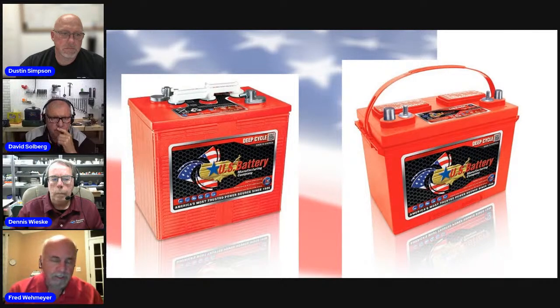Those load testers are really intended for SLI batteries. A true load tester will actually put a discharge on the battery. We have on our data sheets ratings all the way from the 20-hour rate up to the half-hour rate, so depending on the discharge rate on your load tester, you have a rating for every discharge rate you'd need.